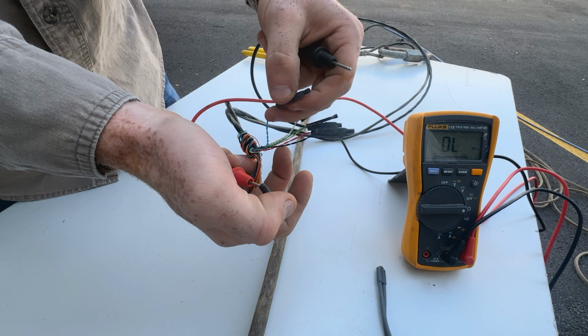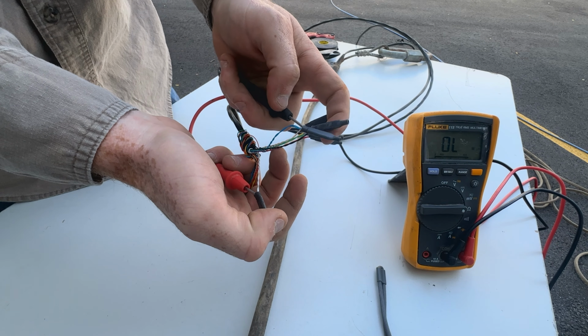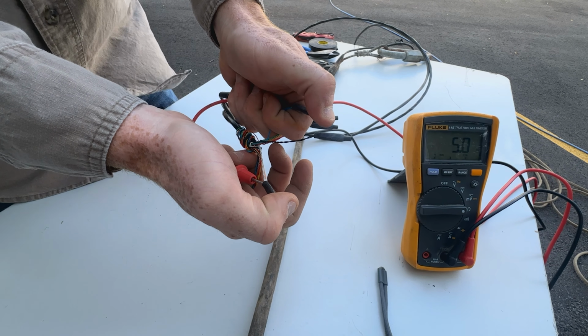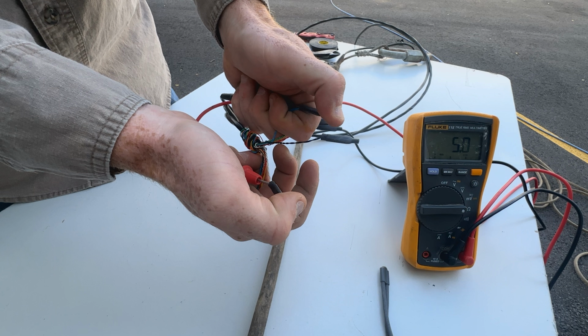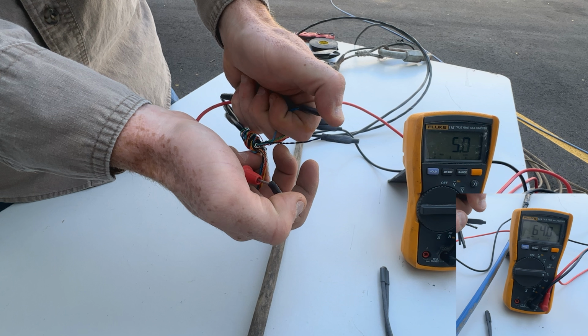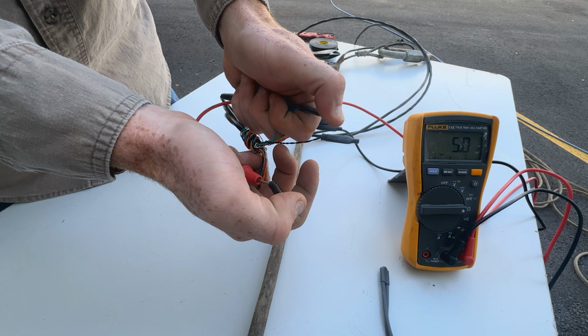Next, we can try the white group, blue wire. Here is an example of another bad thermocouple. Since our temperature cable is 54 feet long, our second to the bottom thermocouple should give a much higher reading. If you remember back to the first cable we did, the second thermocouple gave us a number of 64. Since both of these cables are 54 feet long, these numbers should be about the same.